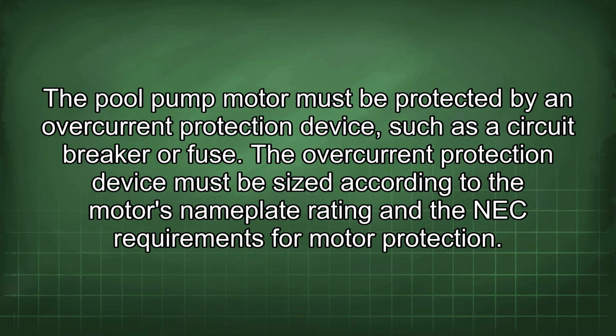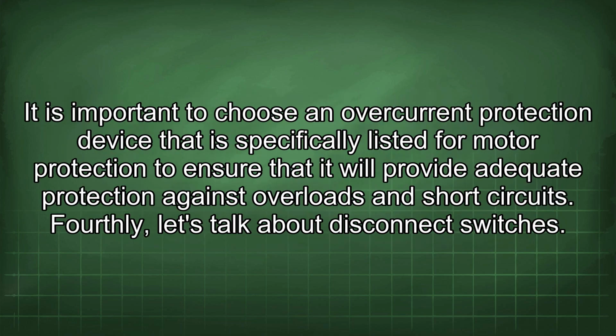The overcurrent protection device must be sized according to the motor's nameplate rating and the NEC requirements for motor protection. It is important to choose an overcurrent protection device that is specifically listed for motor protection to ensure that it will provide adequate protection against overloads and short circuits.